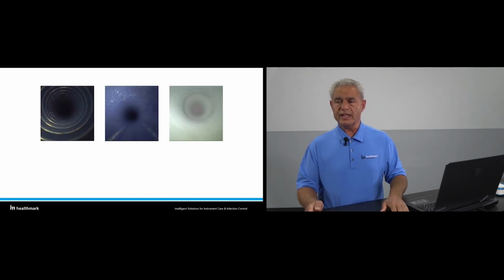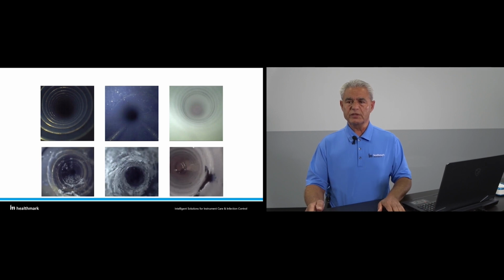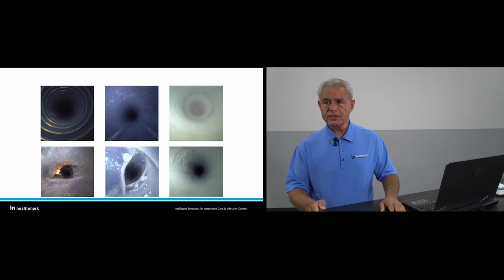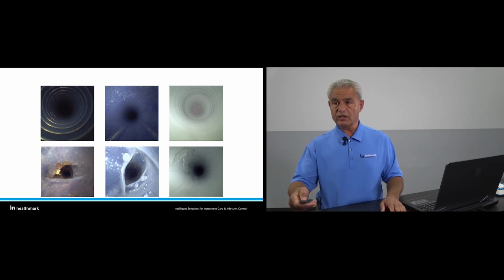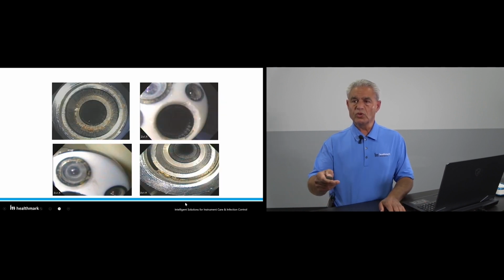So here in that document, it shows an endoscope that is clean, and then what happened when, over time, the debris starts accumulating. Or when the channel starts getting crimps, and you have some issues here where you see a lot of crimping. And when you have those crimps, the material starts accumulating in this area. And here again, you can use a borescope to look inside the distal end and inside the valve and other areas.